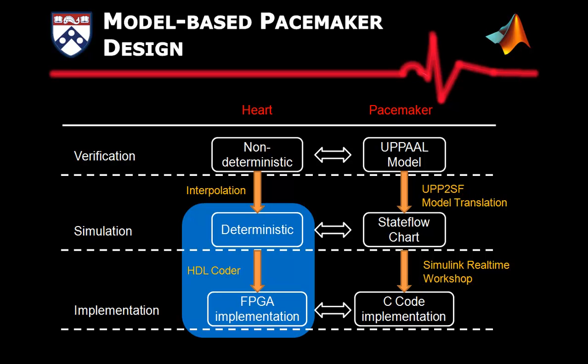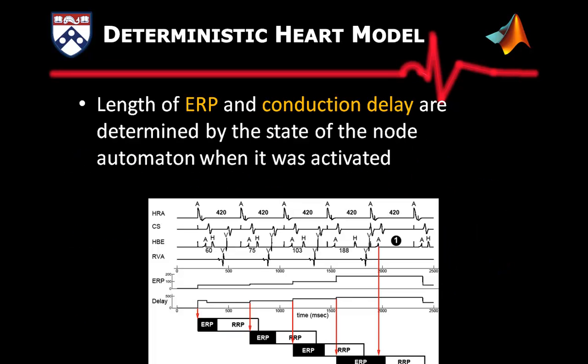Now we introduce our deterministic heart models which can be used for closed-loop simulation and testing of the pacemaker. In a deterministic heart model, we replace the non-deterministic ranges in node and path automata with linear interpolations.